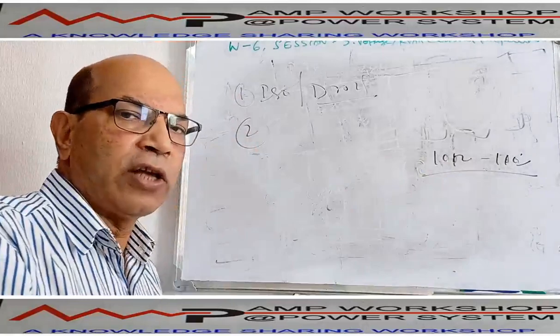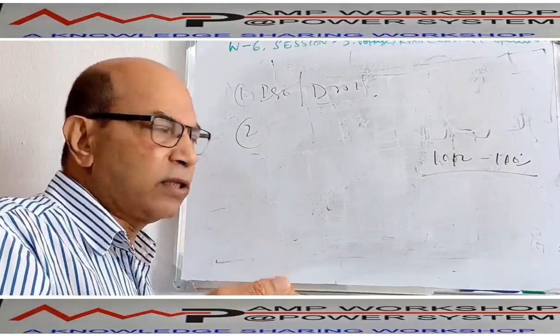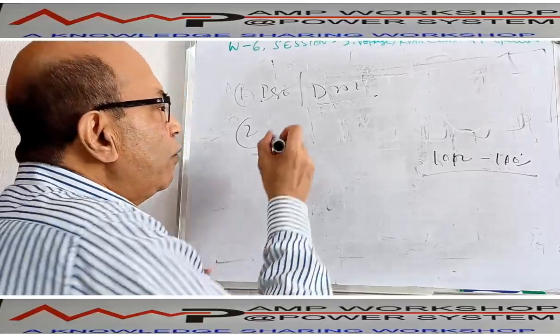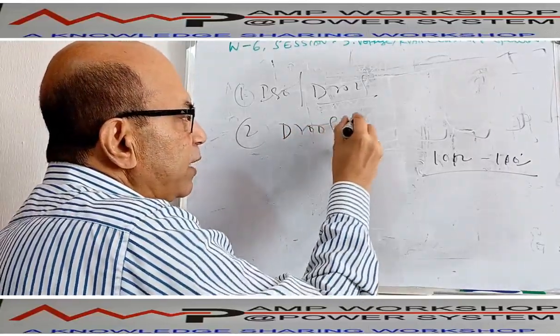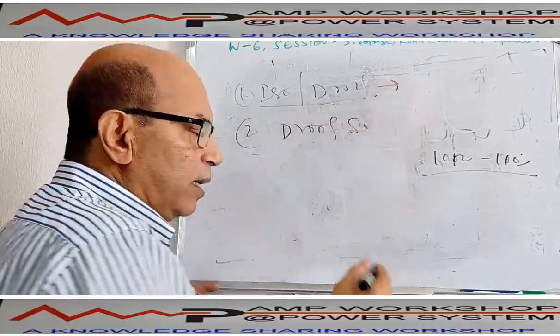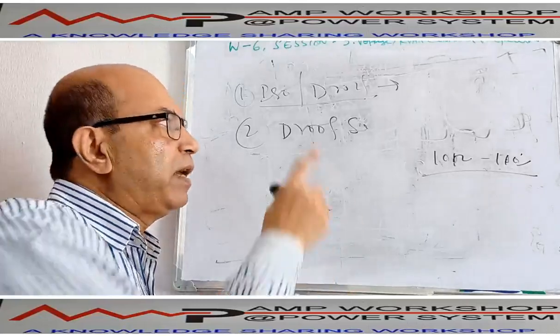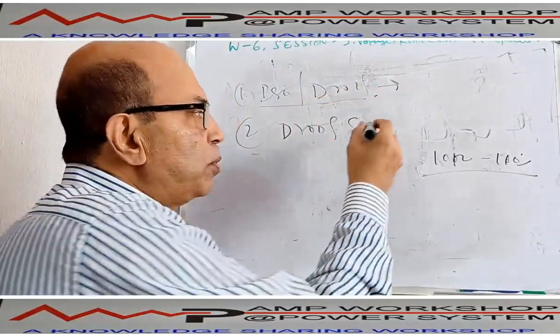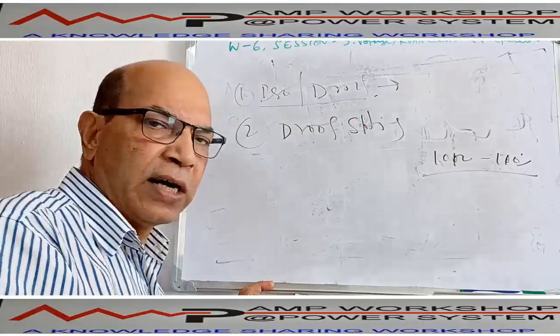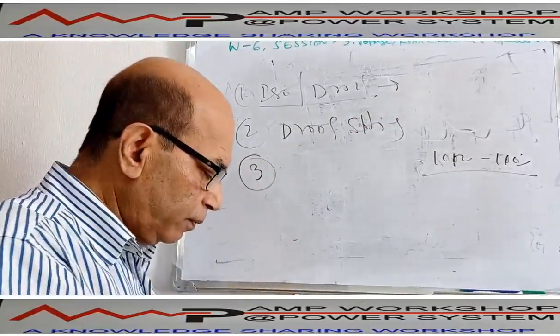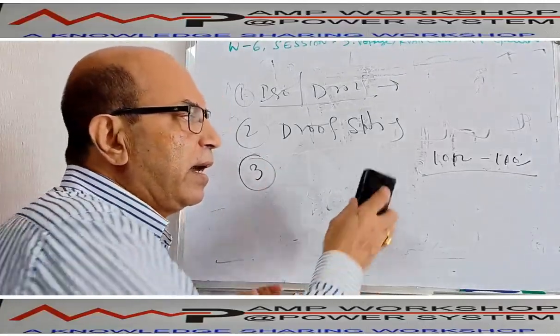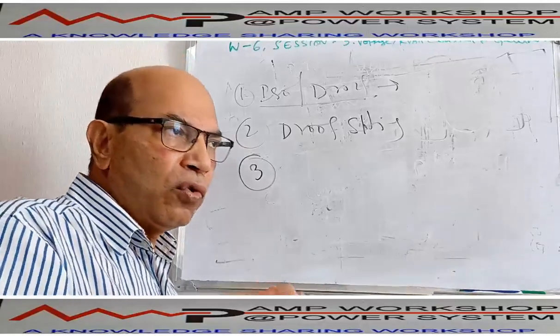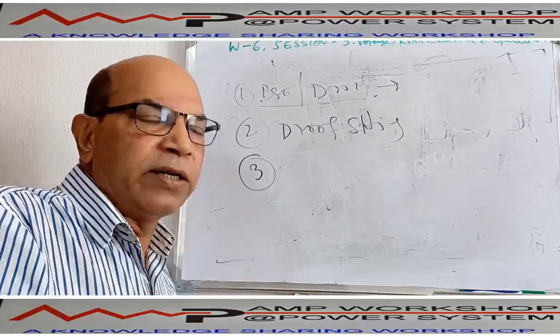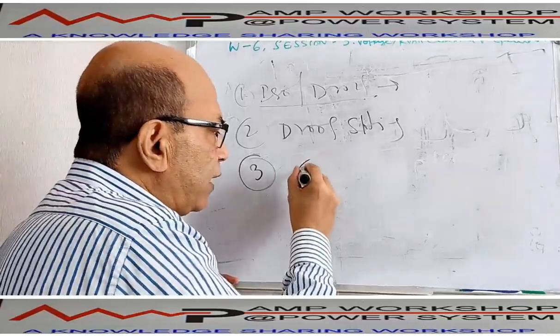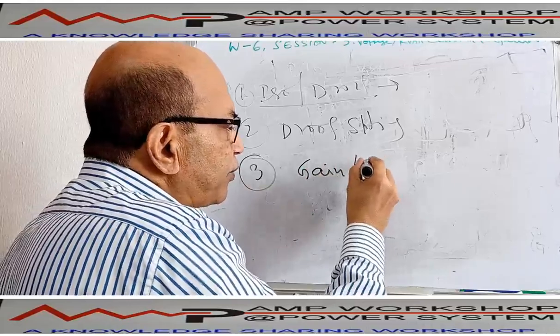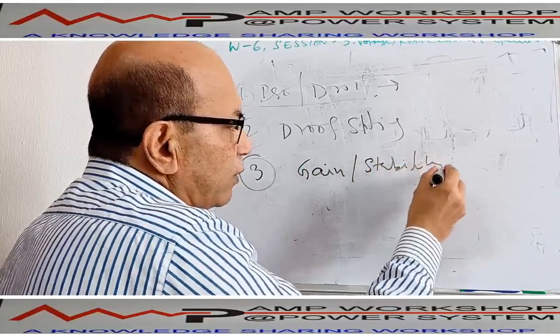But how will we change the setting? So there will be another switch. By rotating the switch, we can change this droop. So there will be a droop change setting or droop setting switch. This is a mode selector switch, two position, either isochronous or droop. That is the selection. But now the value of the droop is to be set by this switch. This is called the droop setting switch. That is another switch. Third switch: this AVR, like a speed controller, can go unstable due to various reasons. So to reduce the gain or increase the stability, there is a gain or stability selector switch that is also available over here. Gain or stability switch is also another switch available.